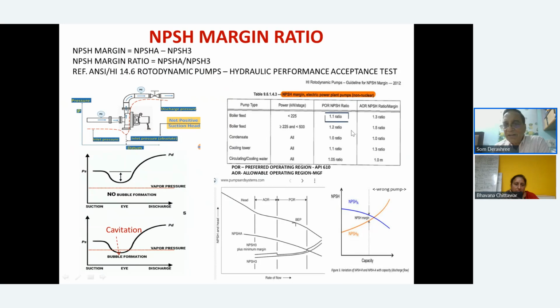Okay, so these are all guidelines at the design stage, when you're doing a selection and the physical layout of the pump, the tank, and the system where it is going to pump. So this NPSH ratio is equally important to keep in mind. And POR is the preferred operating region, and API 610 also mentions this.